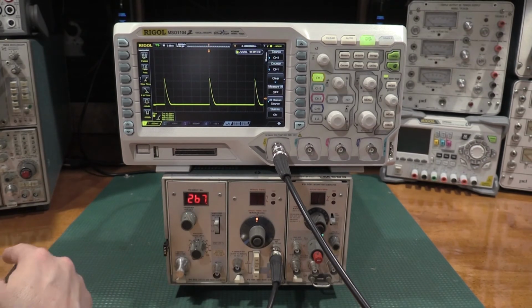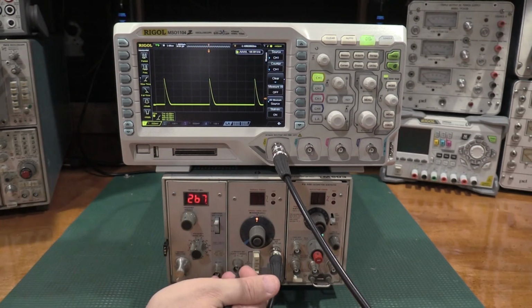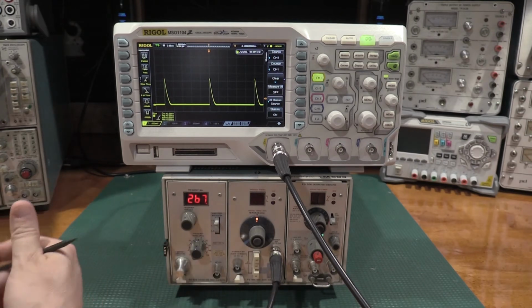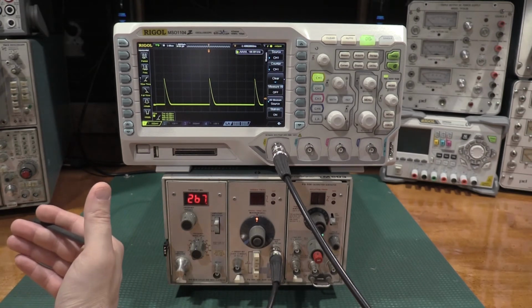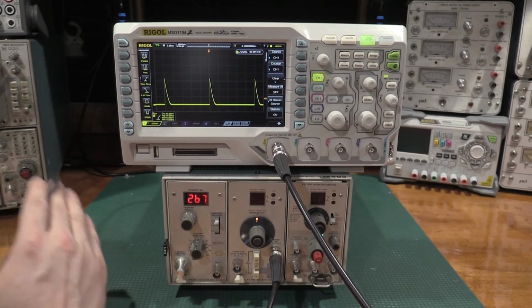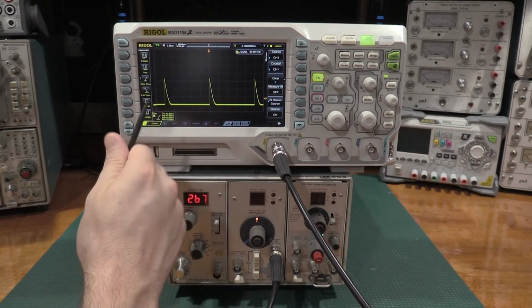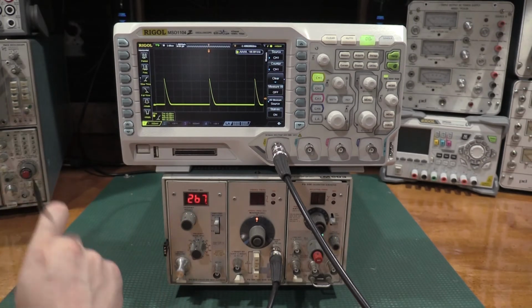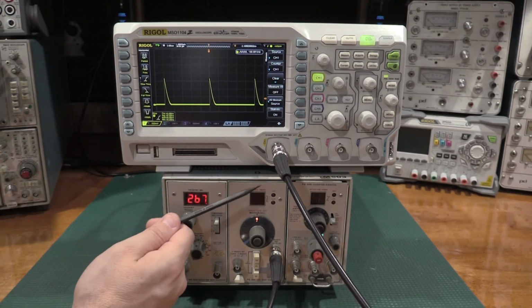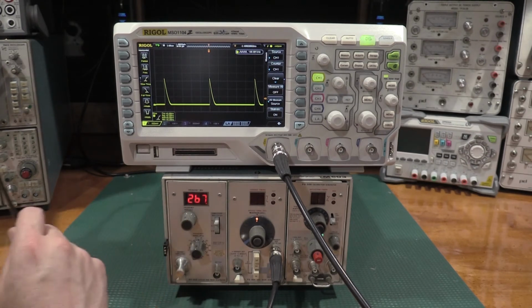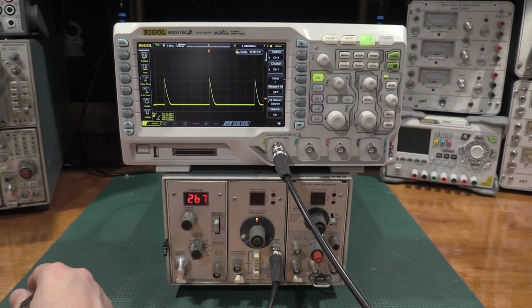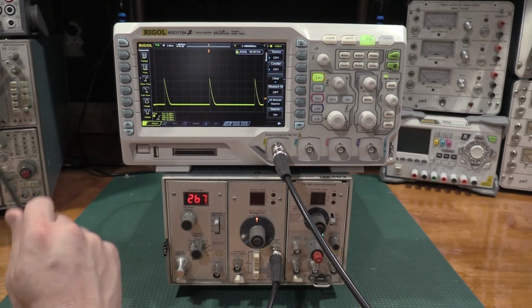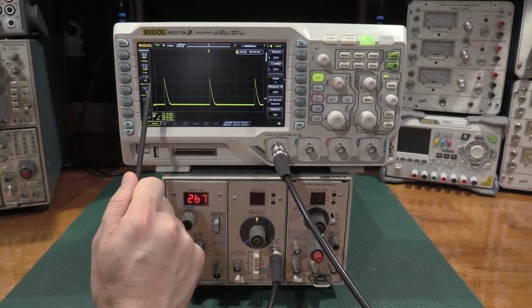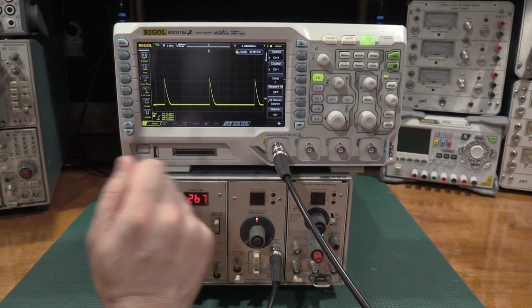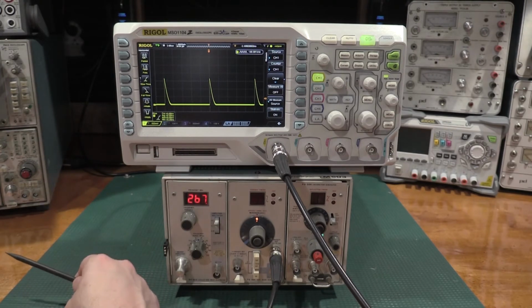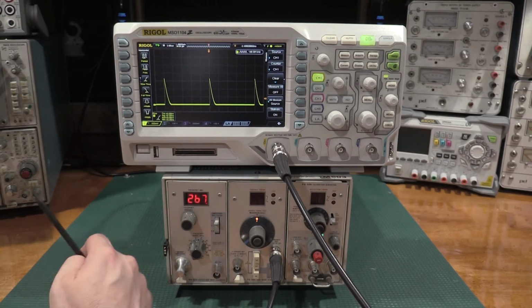So if you were going to substitute a TG501, you would need a pulse, not necessarily a pulse generator, but some way to generate a very sharp rising edge with a very accurate time. Having just done the calibration on the TG501, the accuracy of that is 0.1% to period. So, a sharp rising edge at a very accurate time base. Now, could that be done with an ARB? Probably.